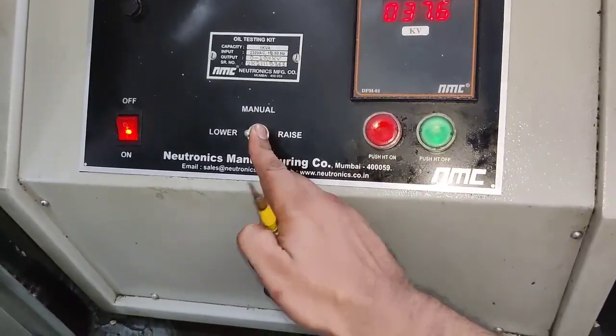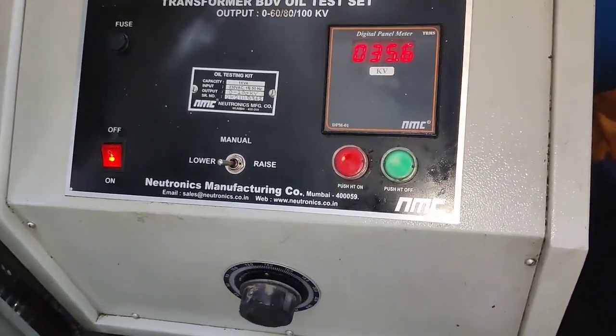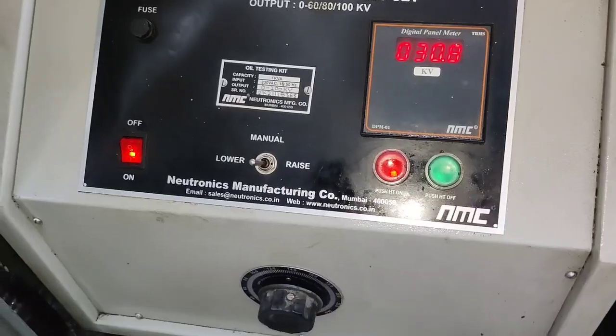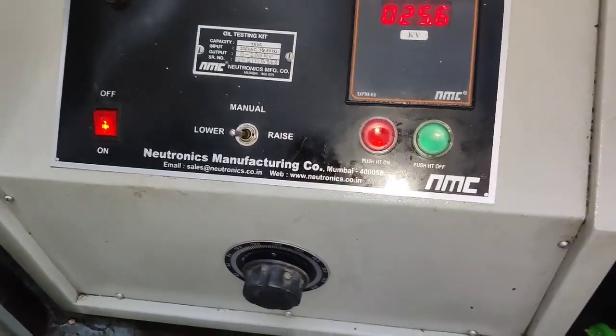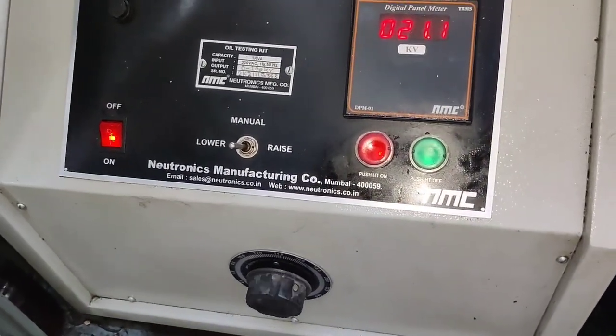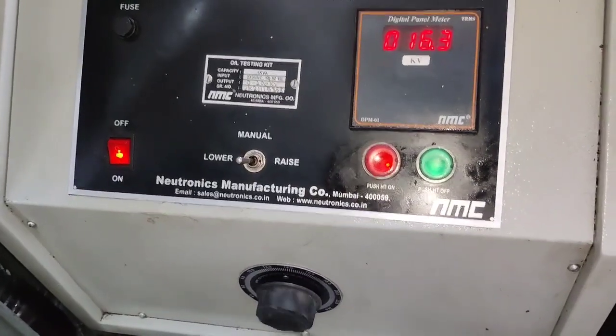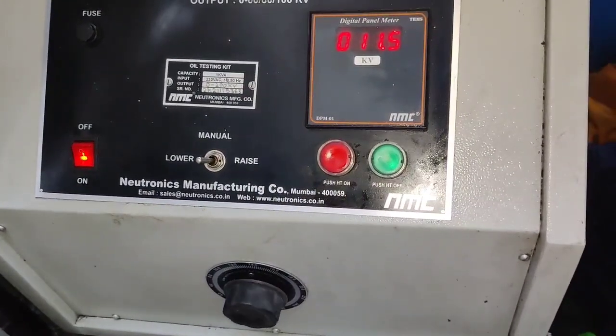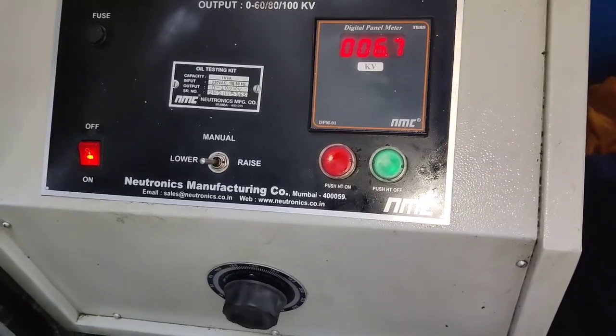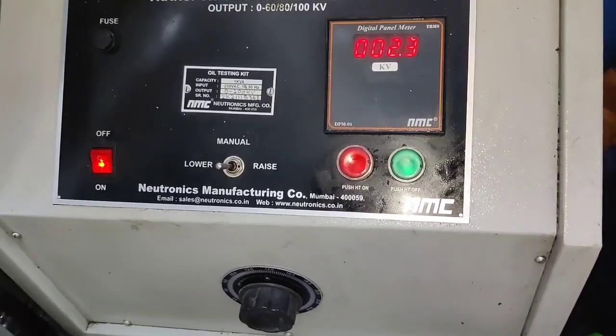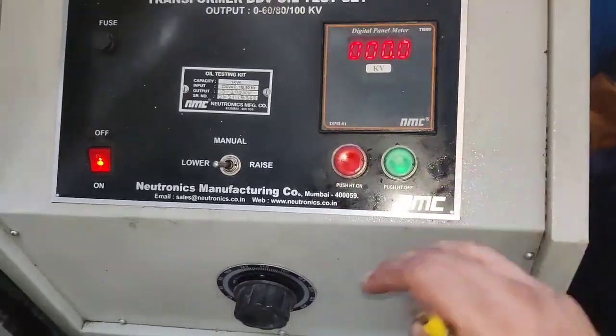Now for resetting the machine, first you set it to lower or manual. When you set manual, your variac decreases automatically and goes down to zero. After it goes down to zero, you can use this machine again. And for testing transformer oil, you can perform this test 4 to 5 times.